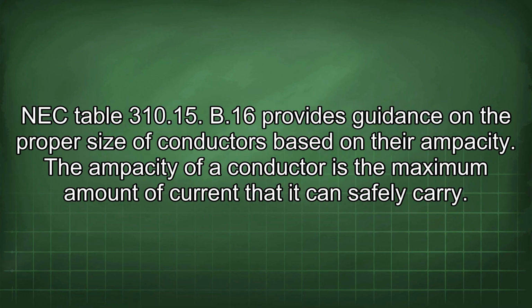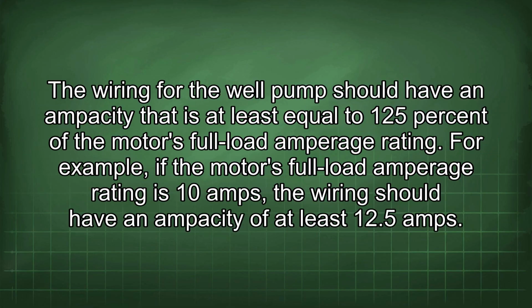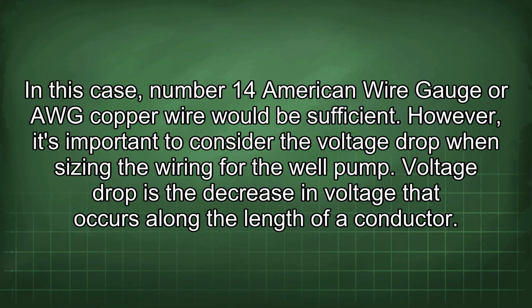NEC Table 310.15(B)(16) provides guidance on the proper size of conductors based on their ampacity. The ampacity of a conductor is the maximum amount of current that it can safely carry. The wiring for the well pump should have an ampacity that is at least equal to 125% of the motor's full load amperage rating. For example, if the motor's full load amperage rating is 10 amps, the wiring should have an ampacity of at least 12.5 amps. In this case, number 14 American wire gauge, or AWG, copper wire would be sufficient.